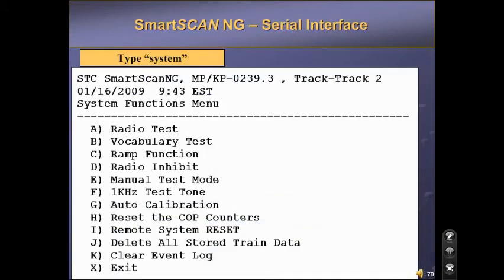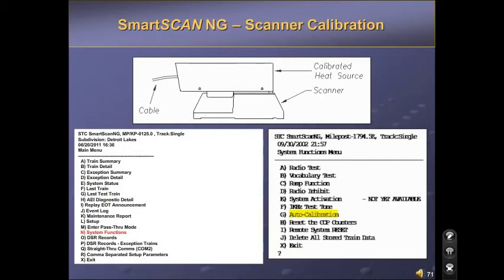This is the System Function menu. This is the menu where you will find many of the test functions on the system. In order to run a calibration, the heat source should be up to temperature and placed on a scanner. Then select the System Function menu and AutoCal. The system will complete the AutoCal unattended.